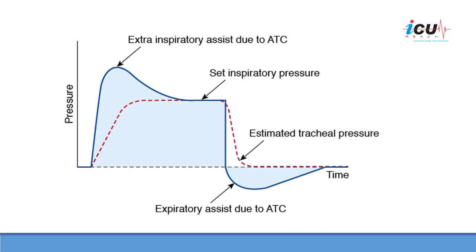ATC applies not only during inspiration but also during expiration. It can deliver a negative value to help the patient exhale. This is the estimated tracheal pressure — the expiratory assist due to ATC is shown on the blue line here, and as you can see, it can drop the pressure to a negative value, facilitating exhalation.